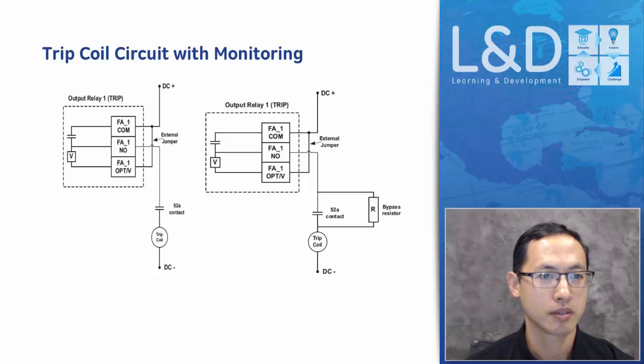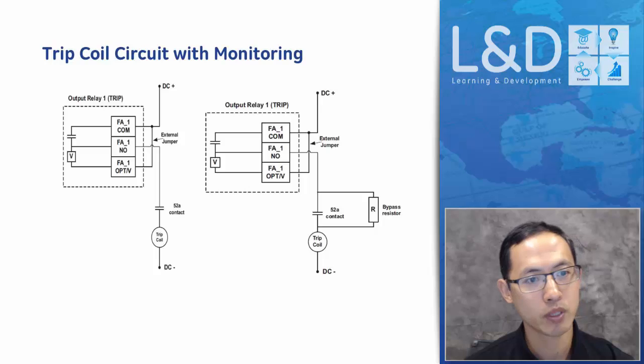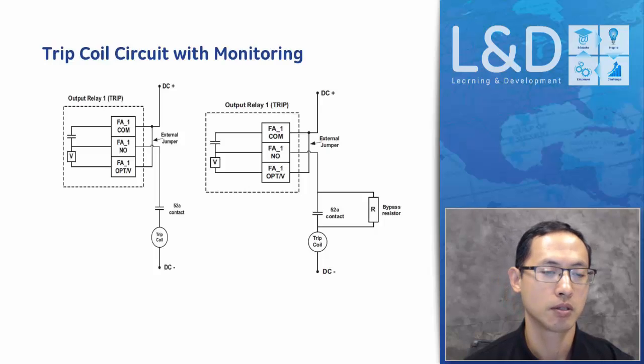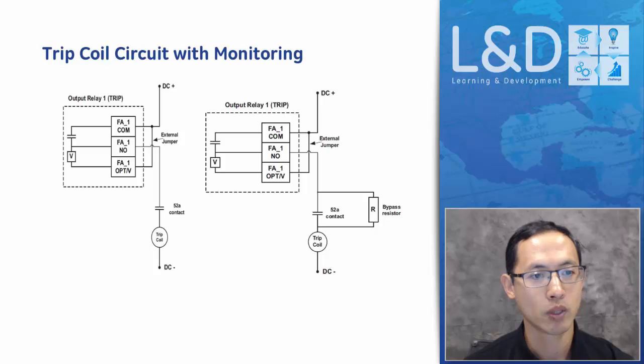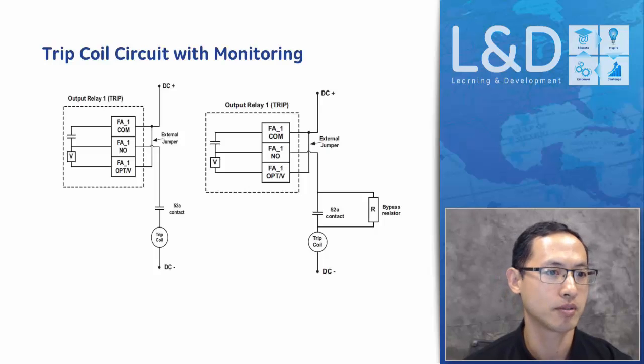Then from the second diagram, when a bypass resistor is connected, that means even without 52A closed, it doesn't matter what the status of the main circuit breaker is. It can always measure the trickle current flowing through the resistors and the trip coil. So make sure that the trip circuit is healthy and can be used to trip the circuit breaker anytime when the fault happens.